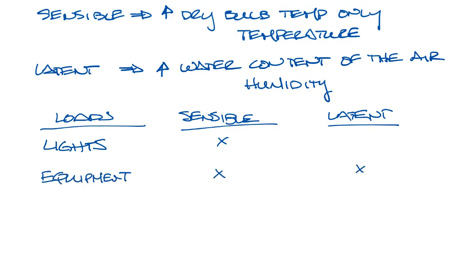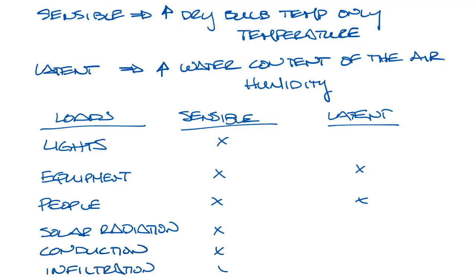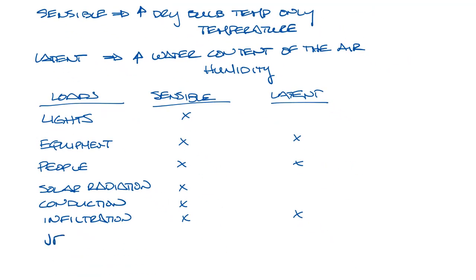Equipment in the building could be sensible or latent, like coffee makers could add some humidity to the building. People are sensible and latent. Solar radiation is sensible. Conduction is sensible. Infiltration from outside can be sensible or latent. Ventilation is sensible or latent. And then your HVAC equipment is usually sensible.